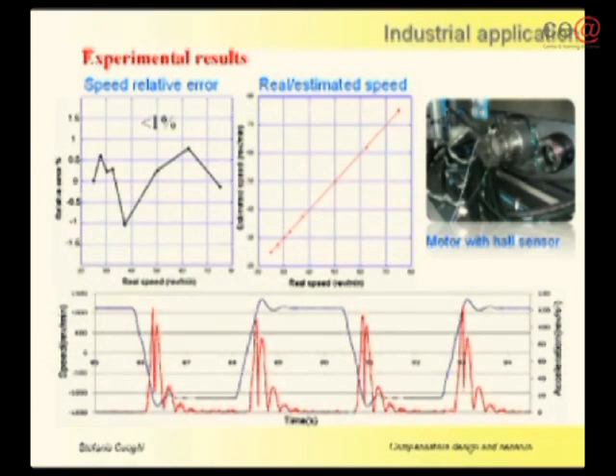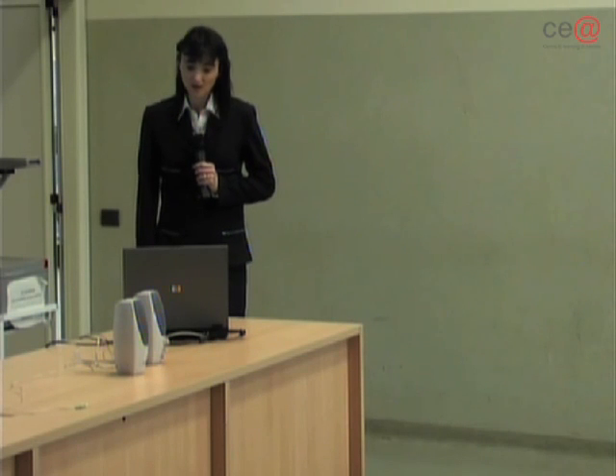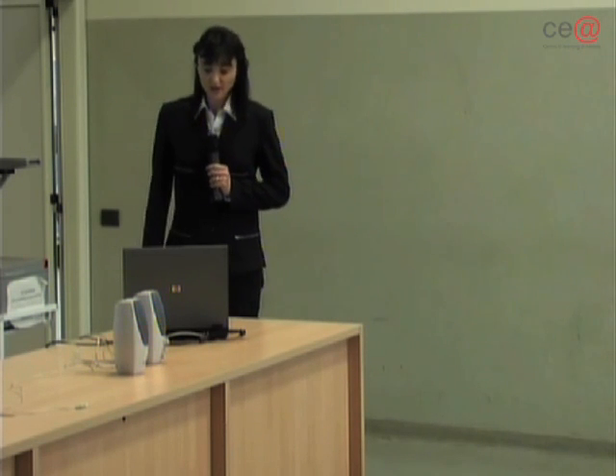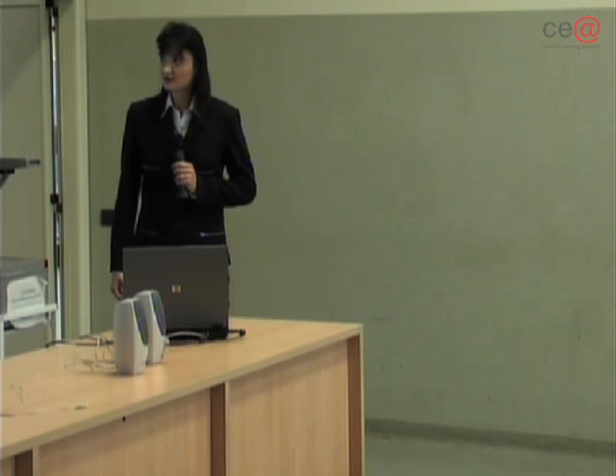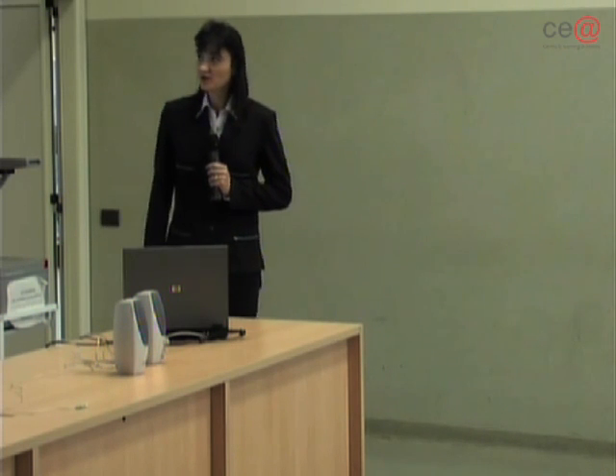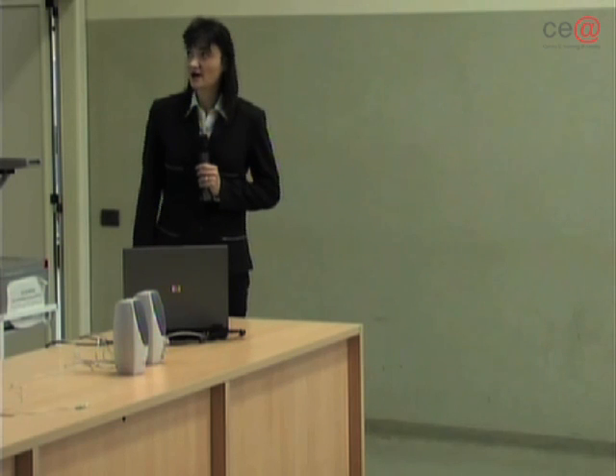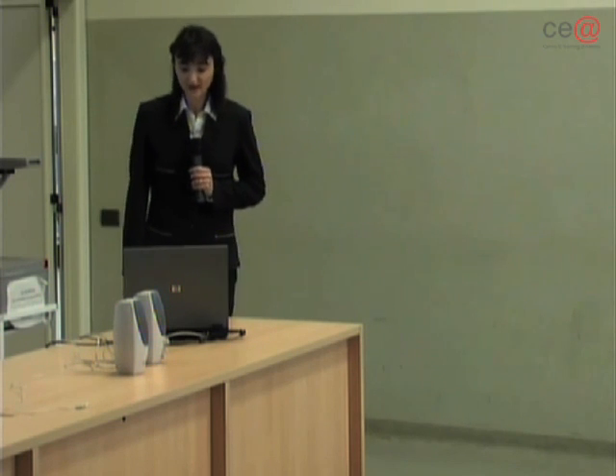Regarding experimental results, tests made in our laboratory and in the company's laboratory confirm the goodness of our project decisions. The system is really able to detect every speed and acceleration variation in real time, with a speed relative error of less than one percent.